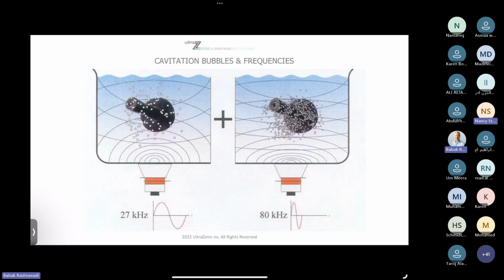That's why you need a higher frequency. Starting from 80 kilohertz and above, you create very, very small bubbles. These small bubbles are tiny but very soft in cleaning, like cleaning with a very soft brush without damaging any instruments. That's why today you have ultrasonic devices with multiple frequencies at once, or you can set a specific frequency. This is something you have to understand.